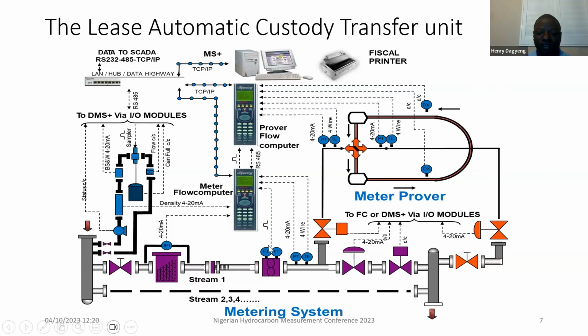Majorly on the LACT unit you have the flow meter, I'm pointing it here with my mouse, and then you have the transmitters here, both for your pressure and your temperature. And then you have the prover here. All the data you are measuring, both your flow and your temperature and pressure, are sent to the flow computer. The flow computer has software, an algorithm that does your temperature correction to base conditions, and then you can store your results on the computer or print them as you may wish.